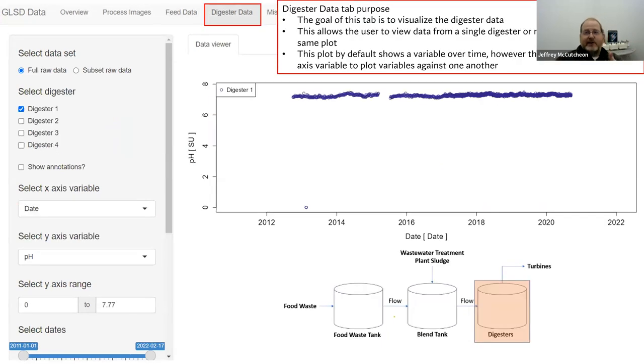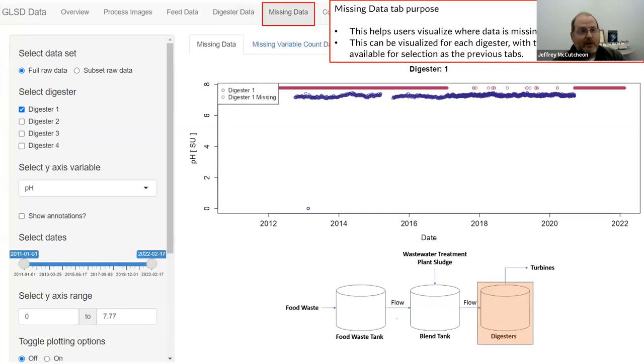We can also look at the digester itself. So here's an example of looking at pH inside the digester as being monitored by GLSD. And we can really visualize this data effectively. And even more interestingly, we can visualize where data might be missing. And this isn't a bad thing, having missing data. Sometimes the sensors go offline or they're not recorded, and that's perfectly fine.